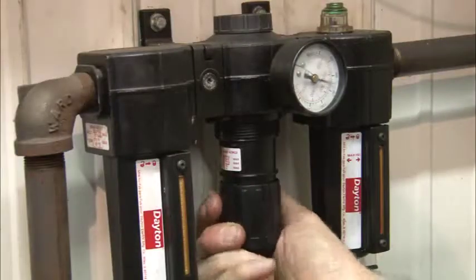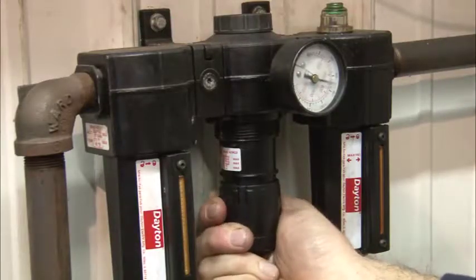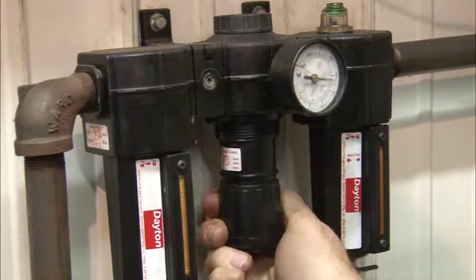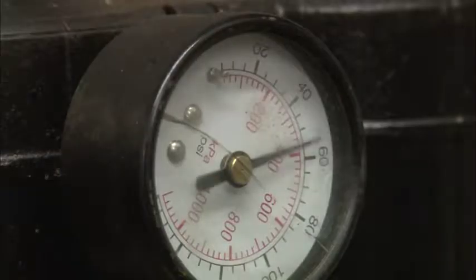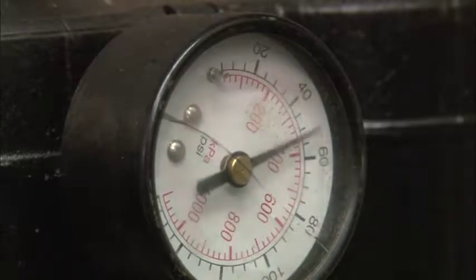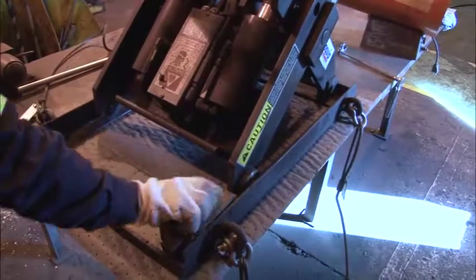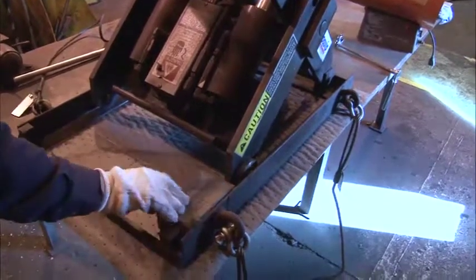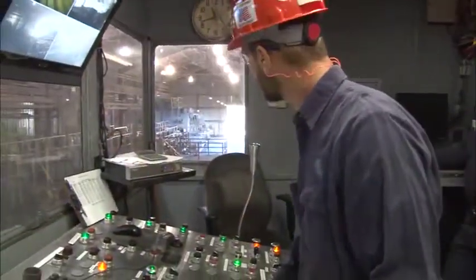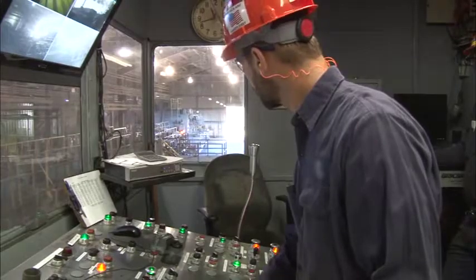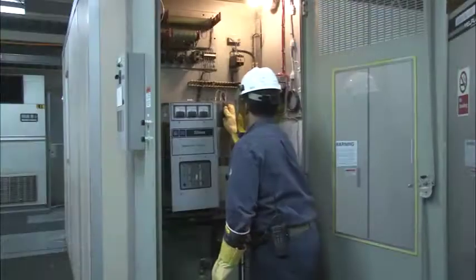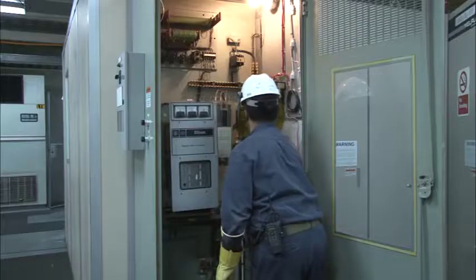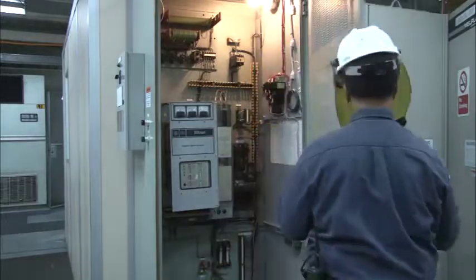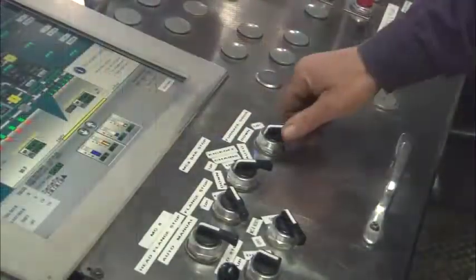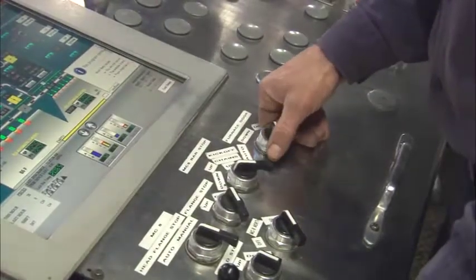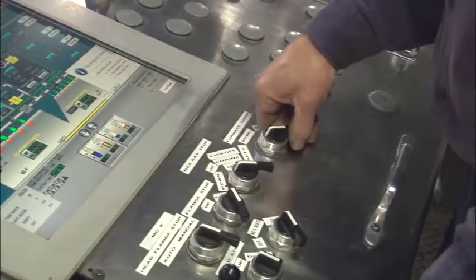The next step involves identifying and neutralizing all potential or stored energy. This includes bleeding stored pressure from cylinders or process lines, venting air or steam pressure, and blocking or securing parts that can move or lowering suspended parts. Finally, the last step involved in the lockout, tagout, tryout process is to test the equipment, or simply put, try it out, or verify through other testing or metering that the energy source is isolated. This is necessary to verify that the equipment is in a zero energy state and will not operate or turn on when the controls are activated.